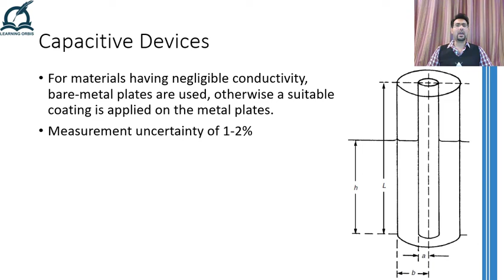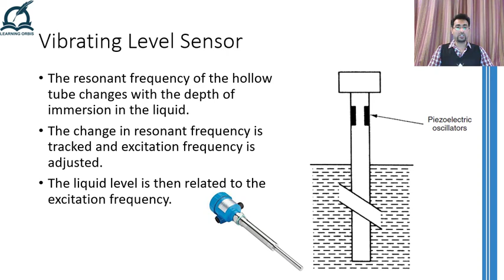Moving on, another very interesting level sensor is called a vibrating level sensor. It consists of a hollow metallic tube that contains piezoelectric oscillators in it. These crystals are used to oscillate the tube at its resonant frequency. However, if the tube is immersed into the liquid, then the depth to which the tube is immersed will dictate the resonant frequency of the tube. Now the excitation frequency of the piezoelectric oscillator is adjusted until the tube vibrates at its changed resonant frequency. At this point, the excitation frequency can be related to the depth of the liquid to which the tube has been immersed.